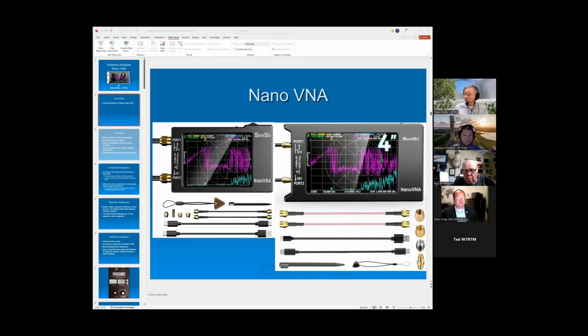The machine on the right, which I kind of prefer, has a larger screen for a little extra price—we'll talk about pricing in a bit. That's a 4-inch screen, much easier to see and configure. Still using a stylus or pick makes life a lot easier going through the configuration. You have the same number of cables and the same slugs for calibration, but it has a nice bright screen, easy to take outside with enough brightness to easily see and calibrate it in the field. That device is also battery operated, with a battery that lasts several hours out in the field. I've easily run 2 hours on mine without a problem—it runs a long time on just the battery.